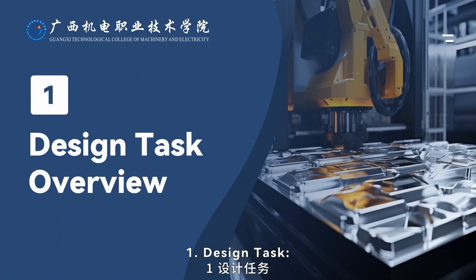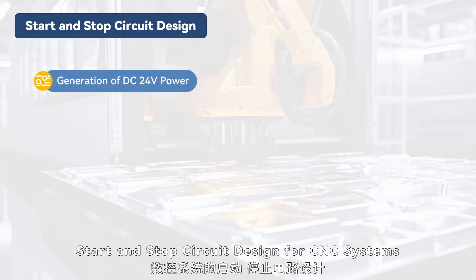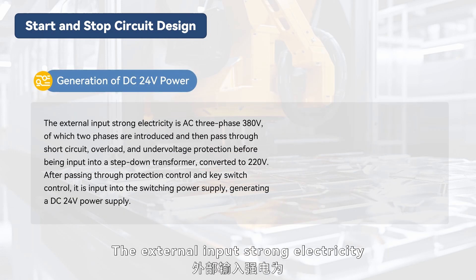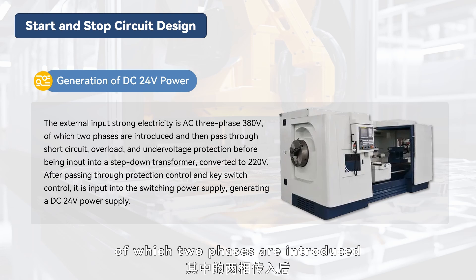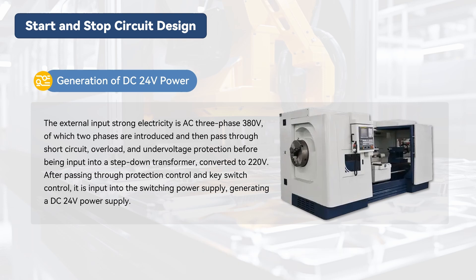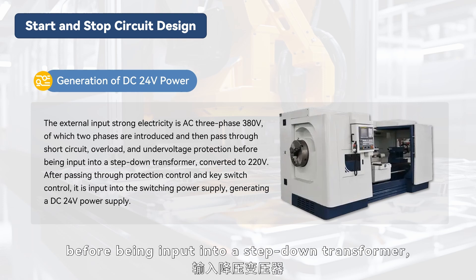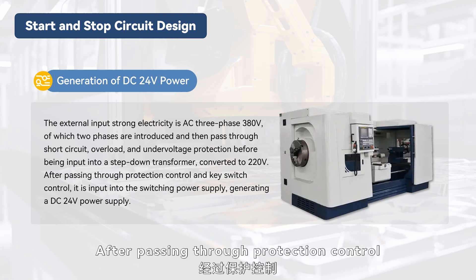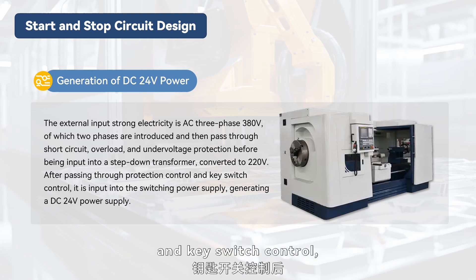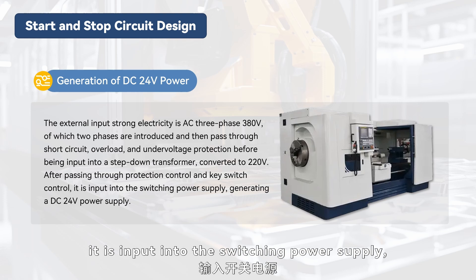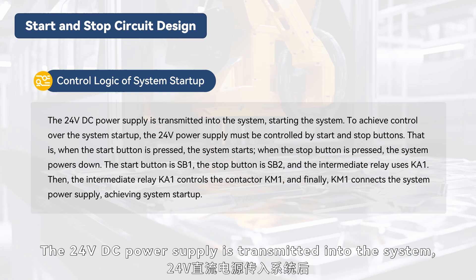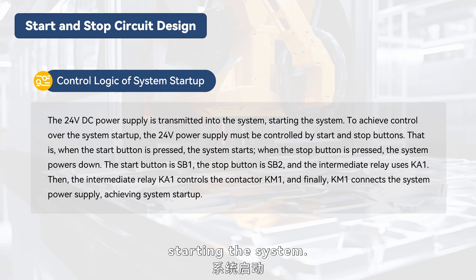Design task: Start and stop circuit design for CNC systems. The external input strong electricity is AC 3-phase 380 volts, of which two phases are introduced and then passed through short circuit, overload, and under-voltage protection before being input into a step-down transformer, converted to 220 volts. After passing through protection control and key switch control, it is input into the switching power supply, generating a DC 24 volts power supply. The 24 volts DC power supply is then transmitted into the system, starting the system.